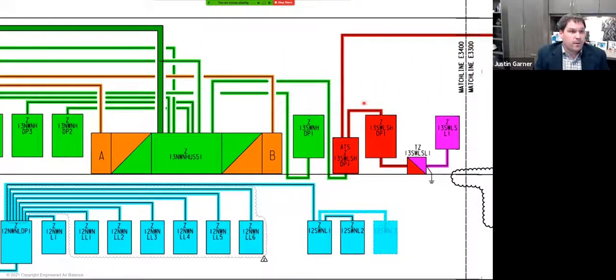So we're going to jump all the way up to the top of this facility. This happened to be up on the 13th floor in the penthouse. And we're going to talk through some of these items here and how they relate to the HVAC systems. So this is a large piece of normal power switchgear. Your orange conductors that you see coming in here, coming in from that 5 kV medium voltage switchgear that we showed earlier.